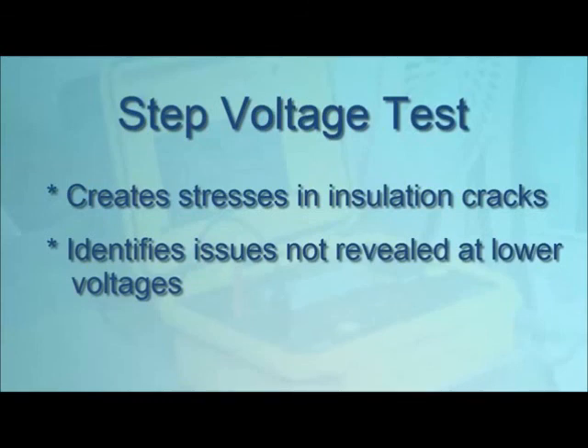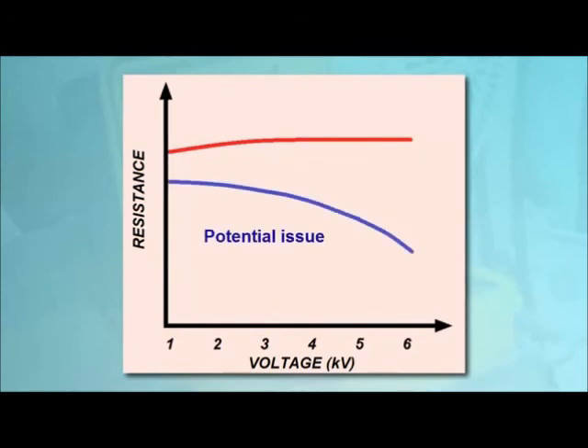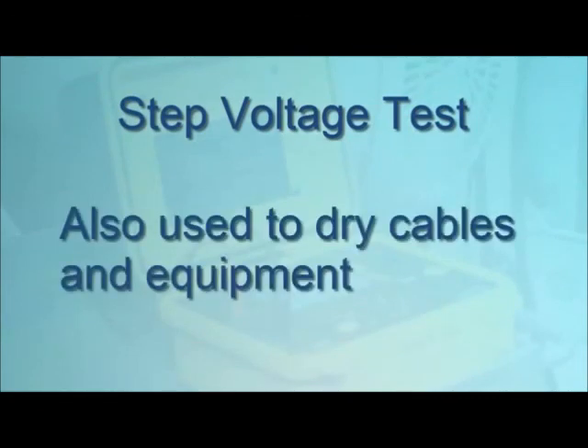Insulation that is thoroughly dry, clean, and in good physical condition should provide roughly the same resistance measurement across the voltage range. If instead you observe a significant decrease in resistance at higher voltages, your insulation may be contaminated or deteriorating. Step voltage testing is also often used as a way to dry wet cables or equipment — gradual voltage steps, applied for increasingly longer durations, can facilitate drying through heating.